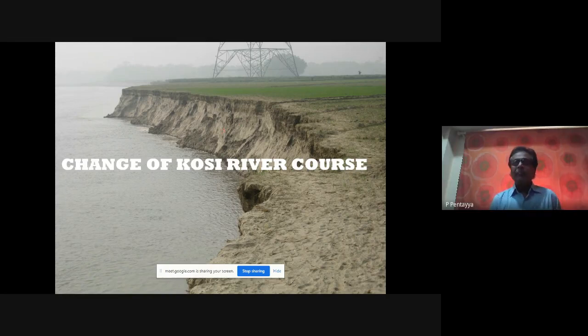So we had to divert this power flow to other routes before tripping the line. That is a very important activity, because during a flood in Bihar on the Kosi River, government authorities and the district collector were all on us, because that line was carrying about 1200 megawatts. We had to reduce and divert the power before we could trip the line, because otherwise boats going below the line for relief measures or evacuating villagers would be endangered.